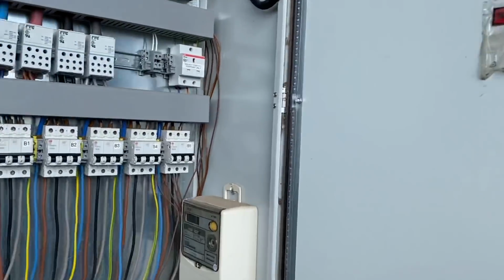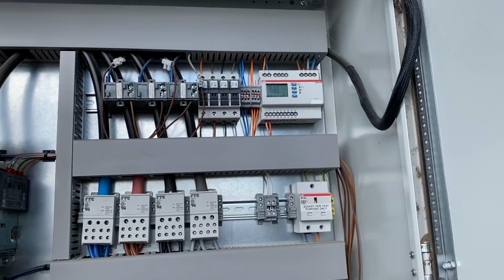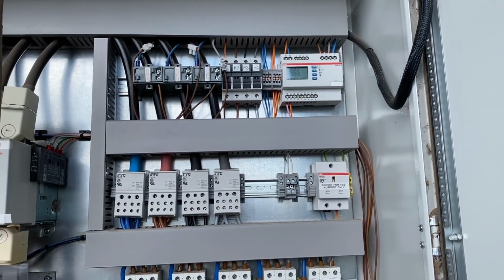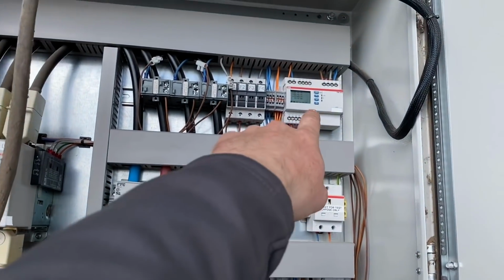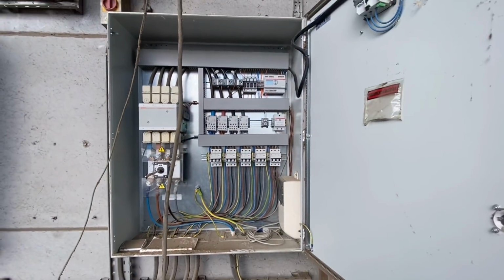Guys here now to upgrade our G59 Relay, some settings in it there. I thought it was having to put a new one on because it was about 2,000 quid of a job and we got a grant towards it. Turns out all it does is change some settings in that and then retest it. Money for old rope, I think.